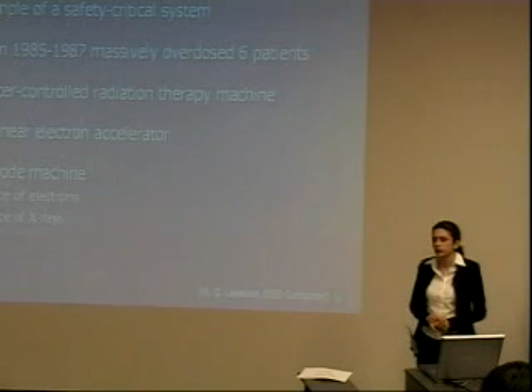Now going into a case study, which is very famous and most of you are familiar with, which is Therac-25. It is a very famous example of an accident which resulted from a small fault in the software of this system. The Therac-25 is a computer-controlled radiation therapy machine. Between the years 1985 and 1987, it massively overdosed 6 patients over North America. The operation of the machine is based on linear electron acceleration. So it has 2 modes for therapeutic reasons. One of them is the X-ray mode. The other one is the electron mode.